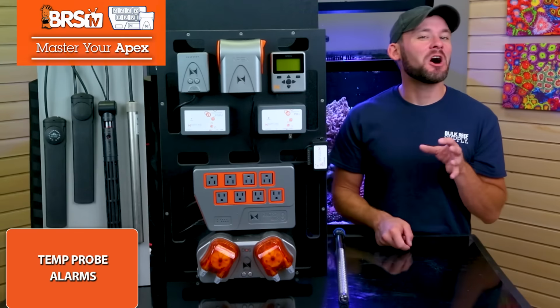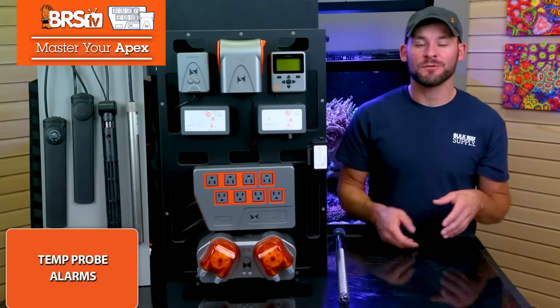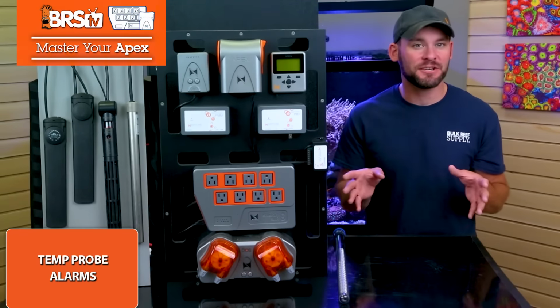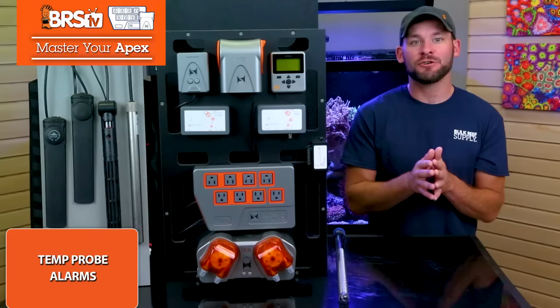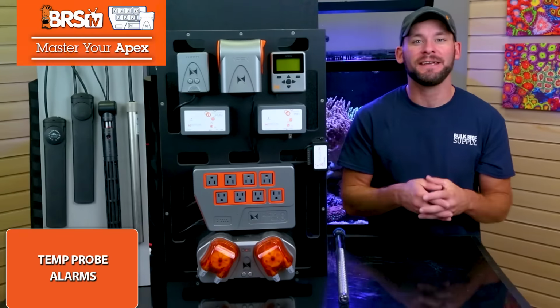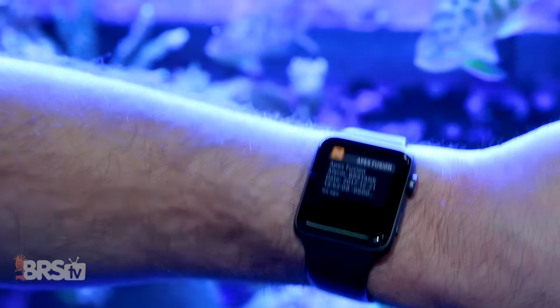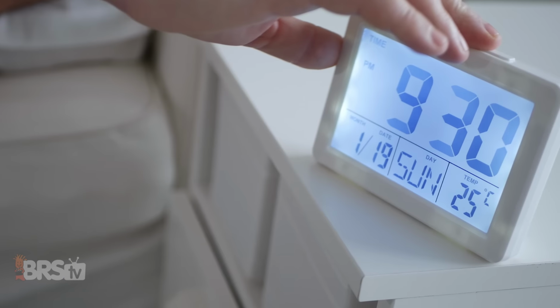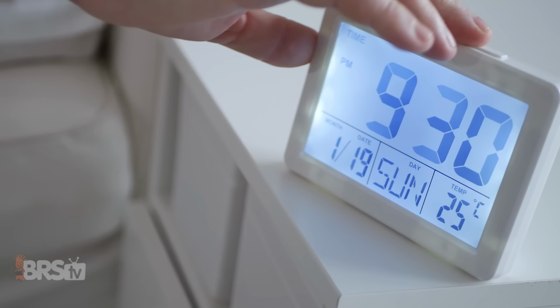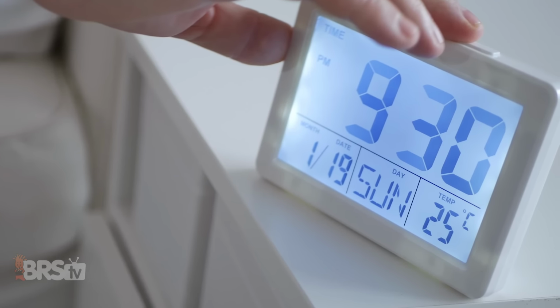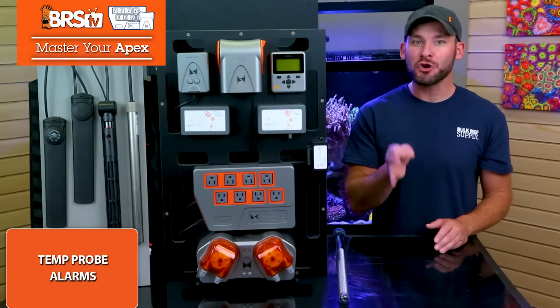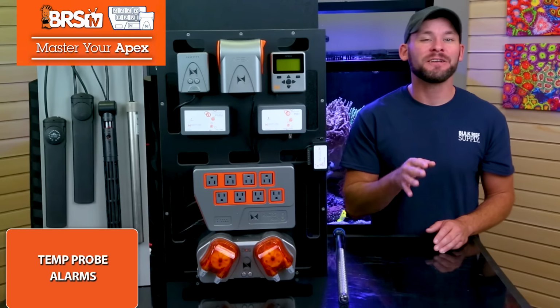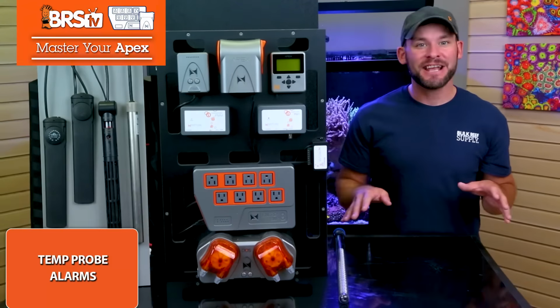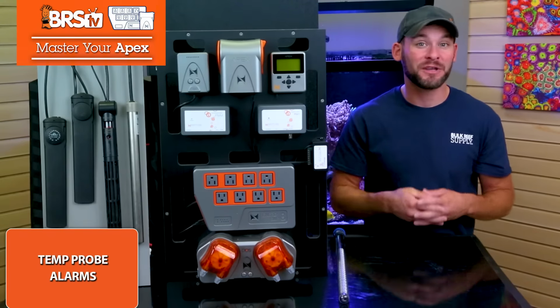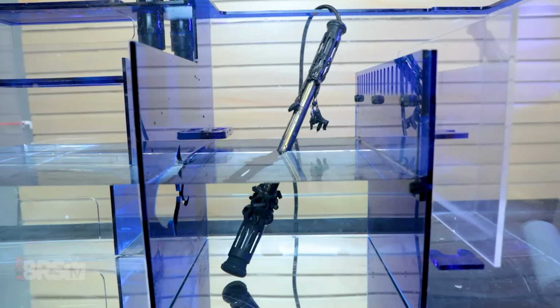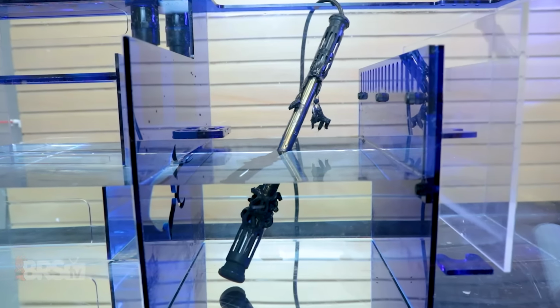I think this type of on-off control really shines when you apply it to emergency notifications. Because the tank temperature is so mission critical to your tank, instead of just a temp alert to your phone or email, you could set up a super loud radio or siren to activate when the temperatures have climbed higher than normal, which is a sure way to wake you up in the event of emergency, eliminate the chances that you miss a temp alarm notification, or decrease the possibility that you wake up to a disaster.